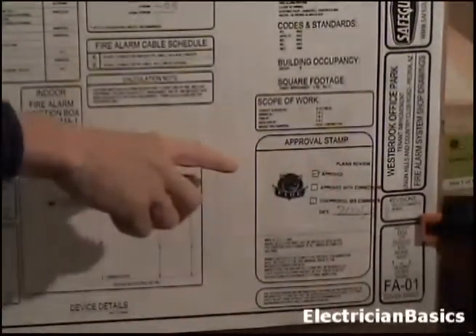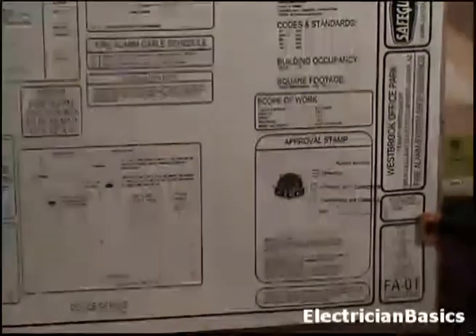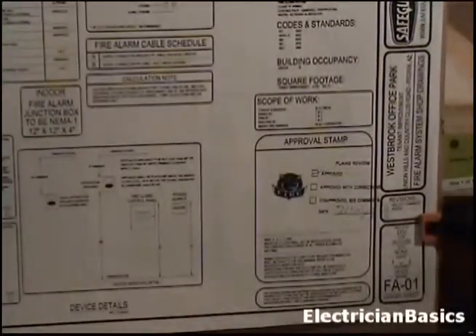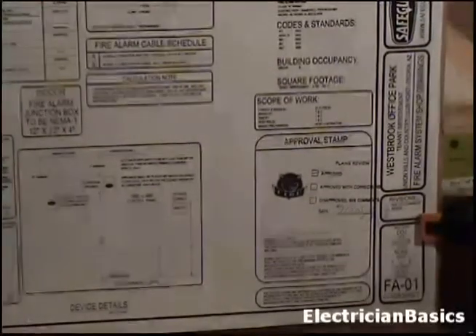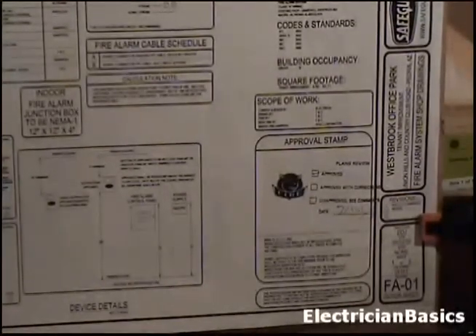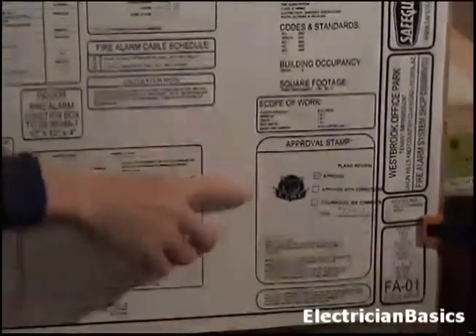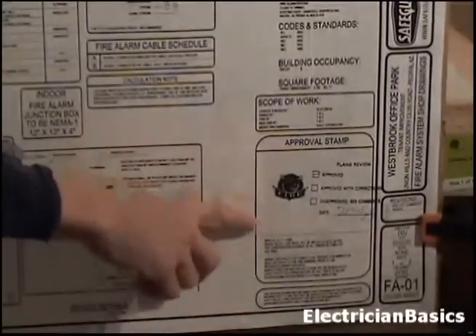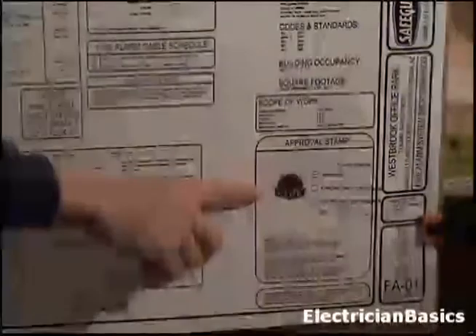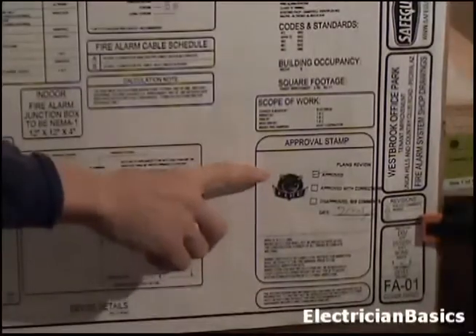This says that the fire alarm system you're putting in is approved by the fire marshal. Now you can't just go in and put in anything you want and say, well, yeah, this worked over here, it should work here. You know, it's not like putting a couple convenience plugs on the wall. This is very, very important, and this approval stamp is very, very important to have. So I just wanted to point that out.